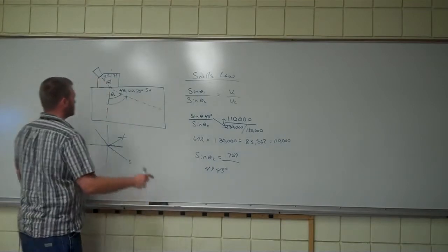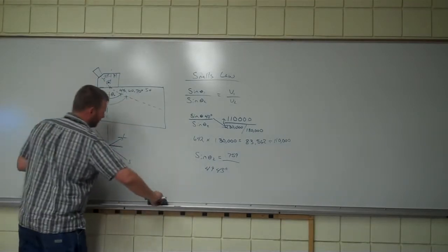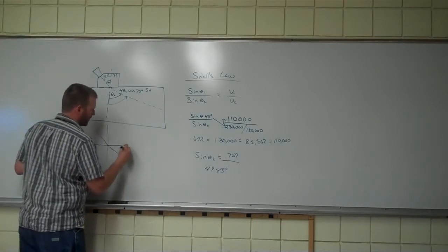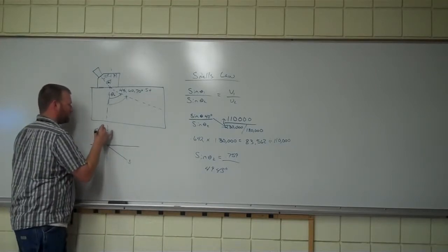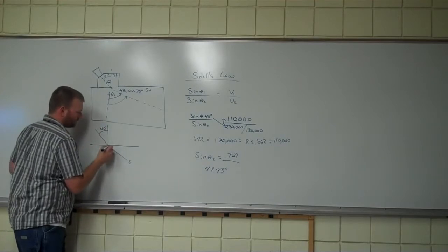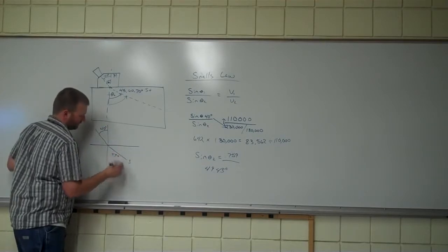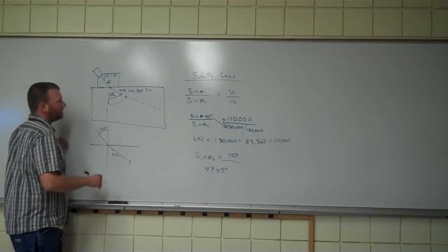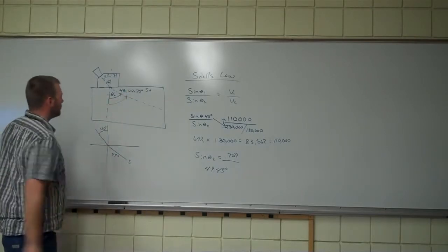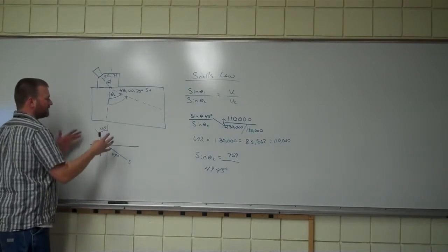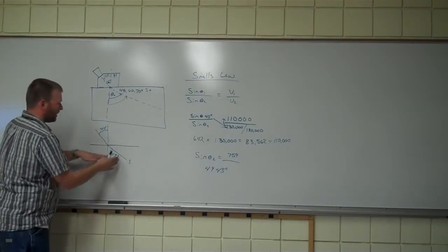Alright, so that tells us this. We're past the first critical angle, so let's get rid of that. The longitudinal wave's gone. At 40 degrees here, we have a resultant shear wave at 49 degrees. A little bit past 45, in between 45 and 60. Nothing wrong with that. It just tells us that with a relationship here, we get a relationship here.